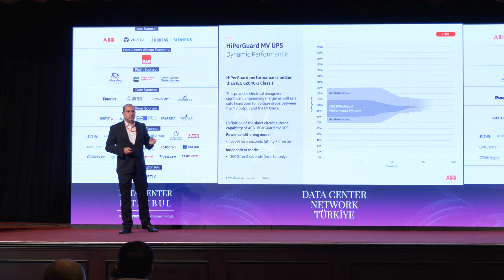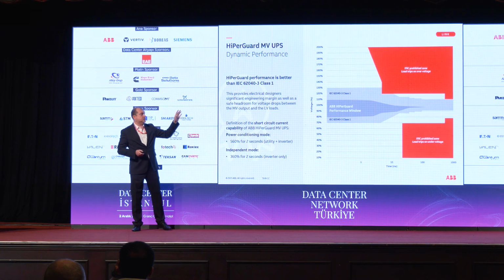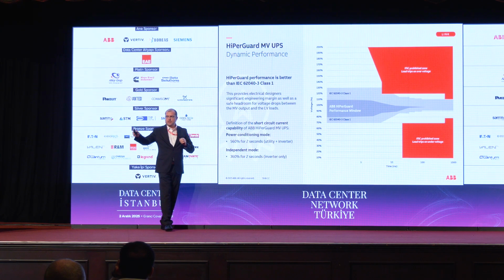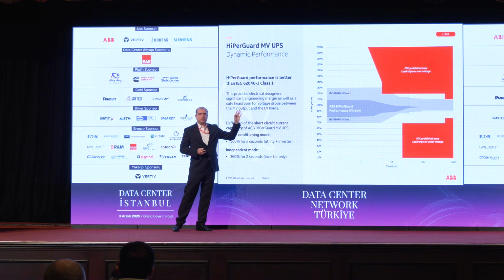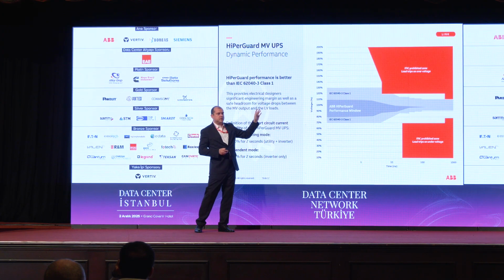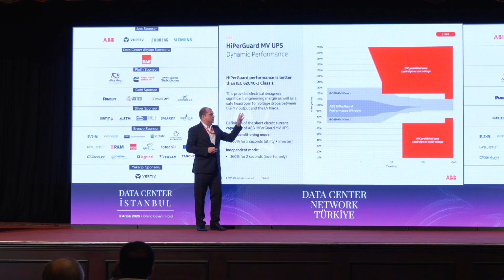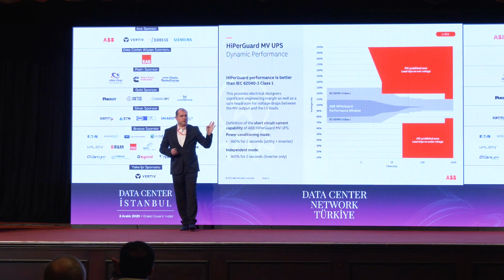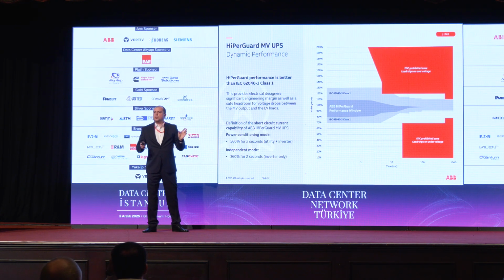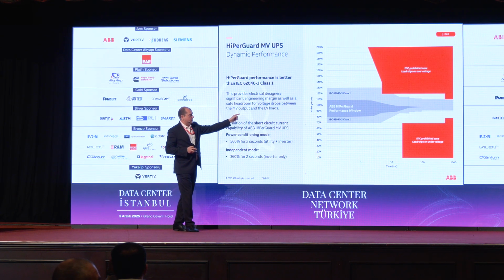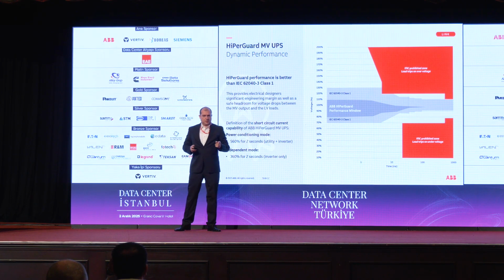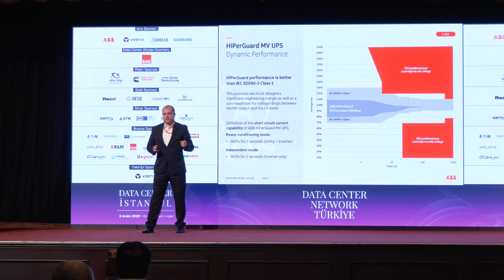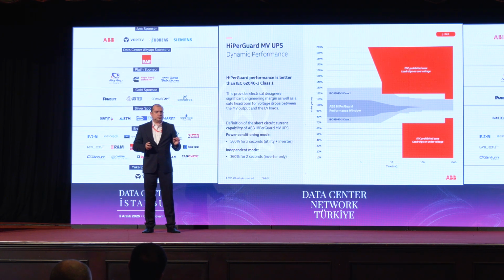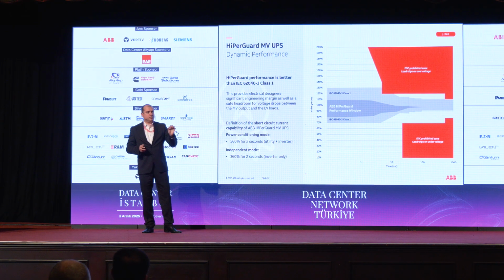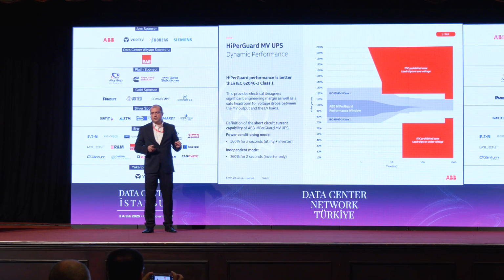Now, I told you about the input phenomena. Now this is on the output. This is the other side. This is how we protect the load. This is the performance of the UPS. We are all acquainted with IEC 62040-3, and class 1 is the most stringent class of all. Here, we have the indication in the dark gray area about the typical performance of the medium voltage UPS. So the idea is to have state-of-the-art dynamic responses. You will see a bit later why this is important.